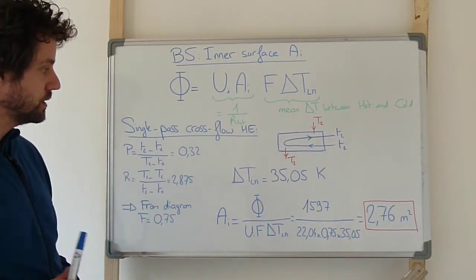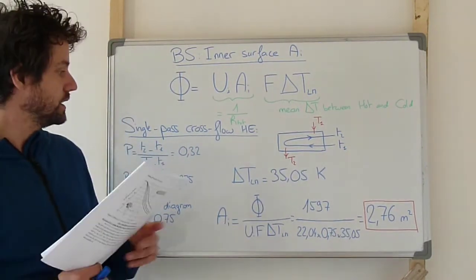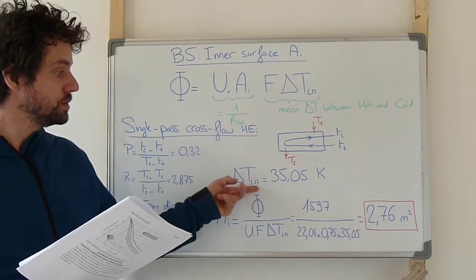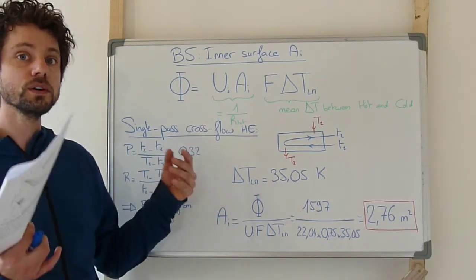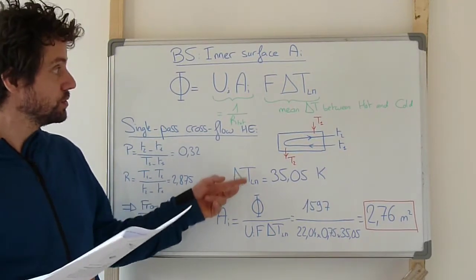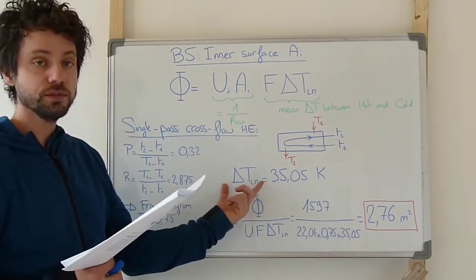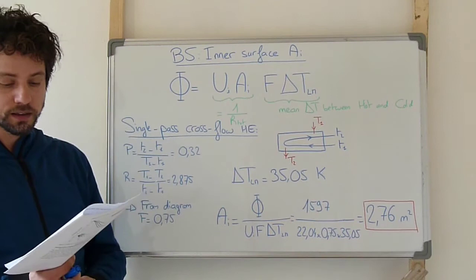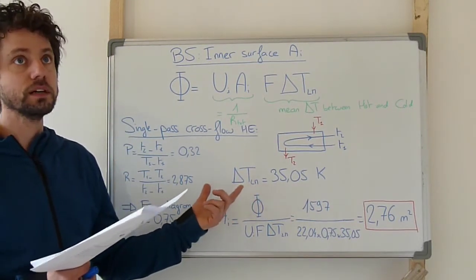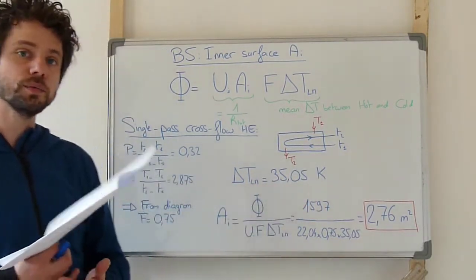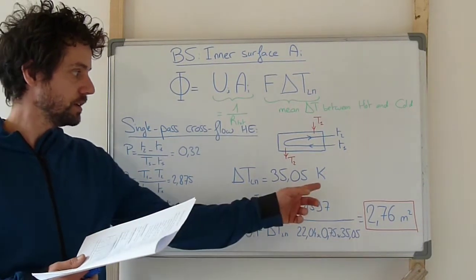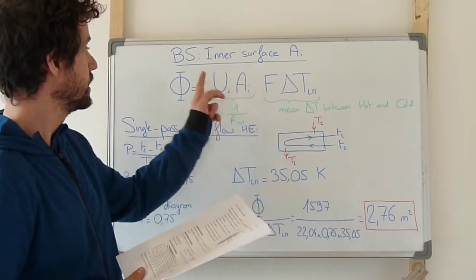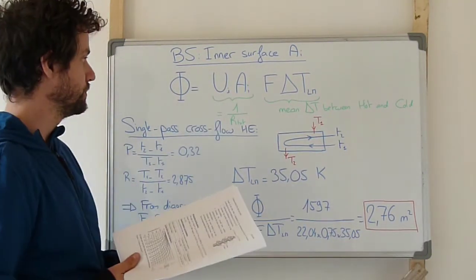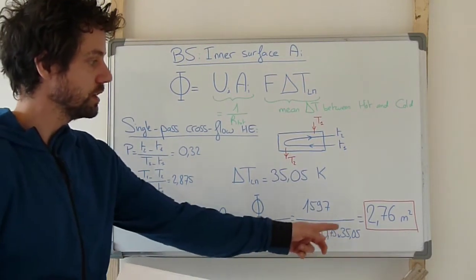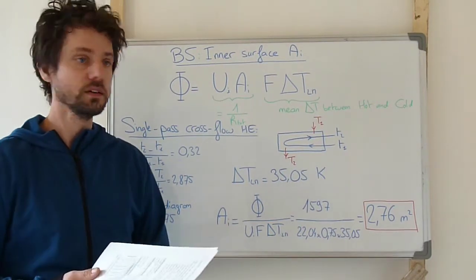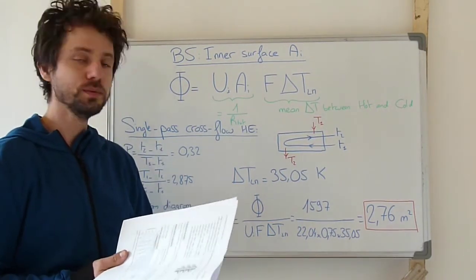Once I have the correction factor, then I need to calculate the LMTD. Here we need to use the expression of the LMTD as if it was a counterflow heat exchanger. This is due to the use of this correction factor. So if you take the expression of the LMTD as if it was a counterflow heat exchanger, you find an average temperature difference of 35.05 Kelvin. And then once we know everything, we can just calculate the inner heat transfer area, and if you do the calculation, you find 2.76 square meters. So that's a large surface that we need for this heat exchanger.